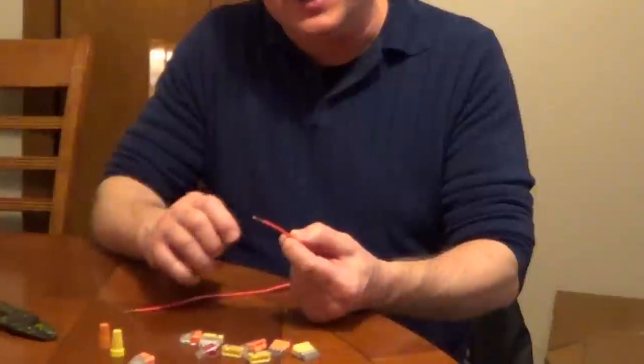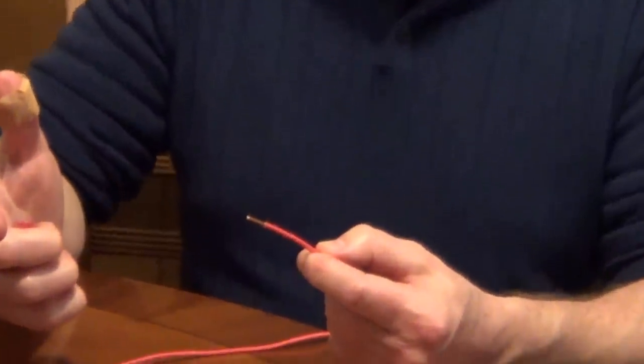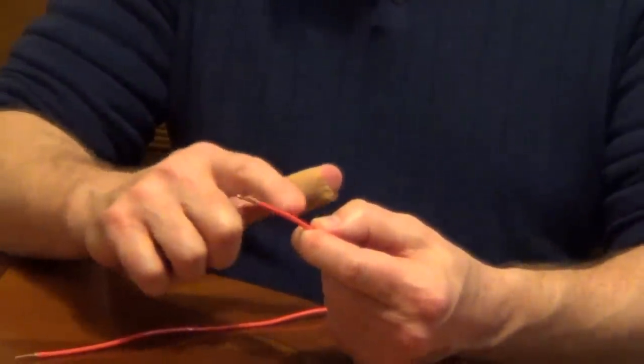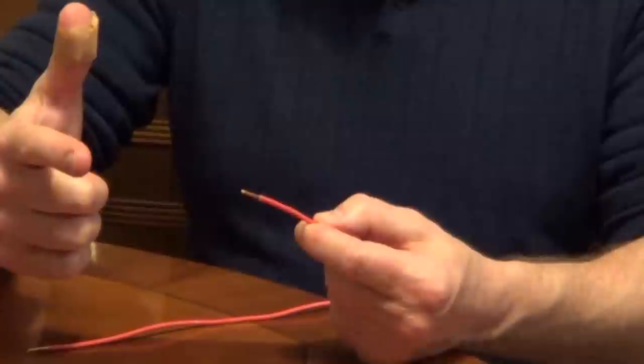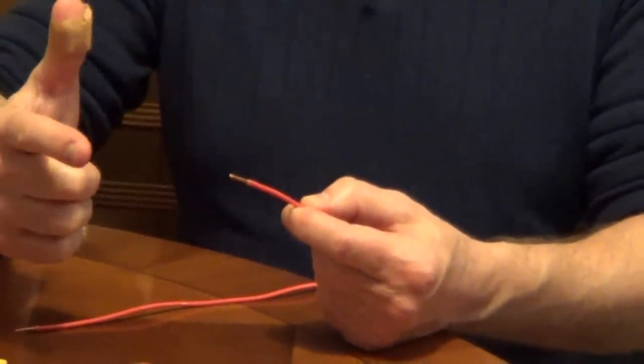I want to share a tip. If you have a wire that's too short in an electrical box, in most codes you have to check with your local inspector, but you should have six inches of wire extending past your electrical box.